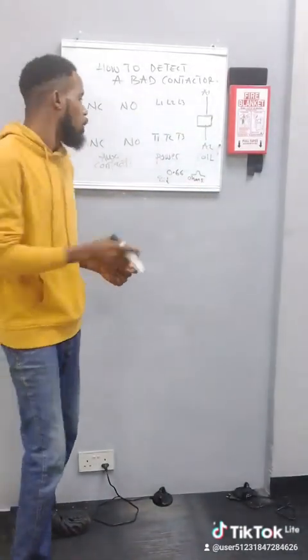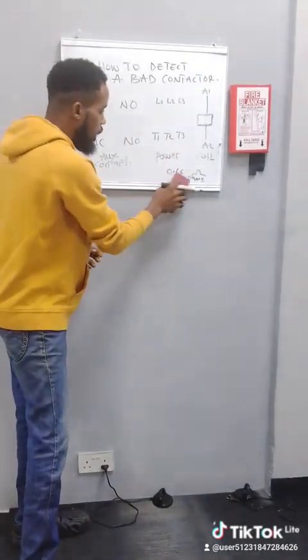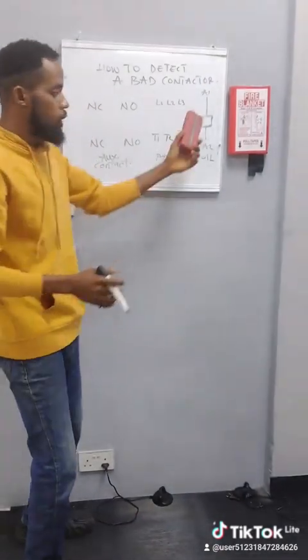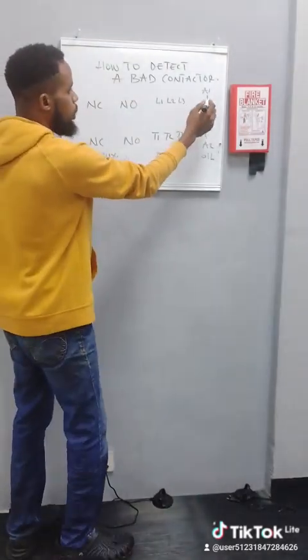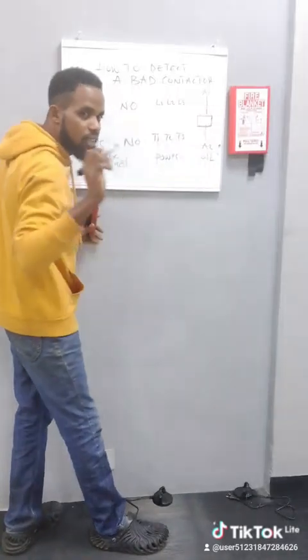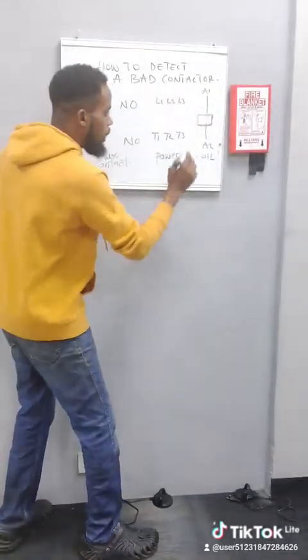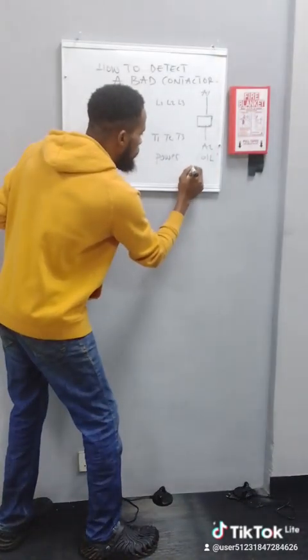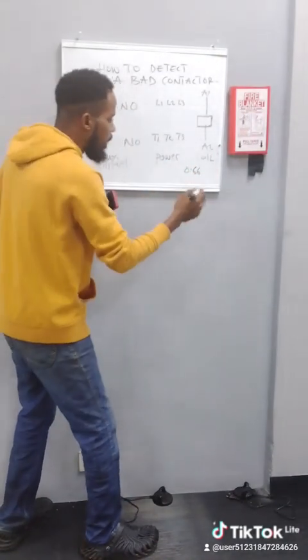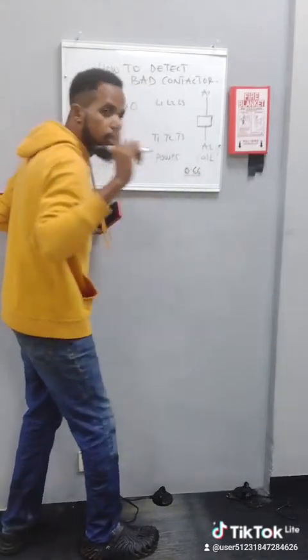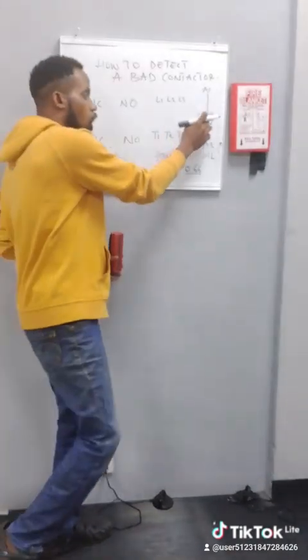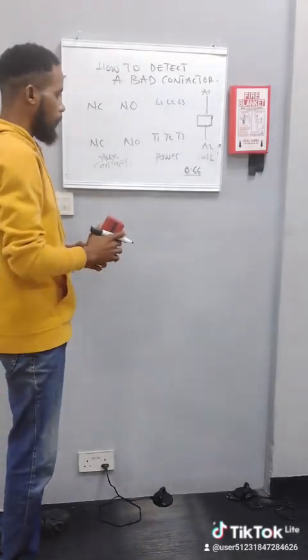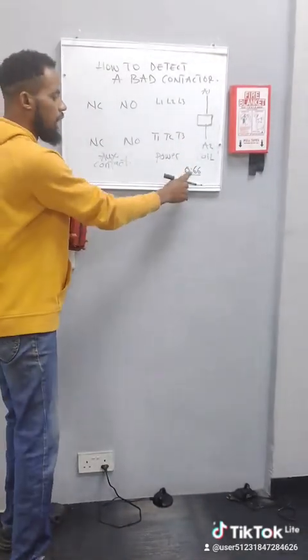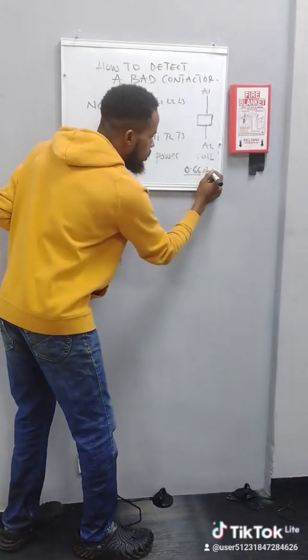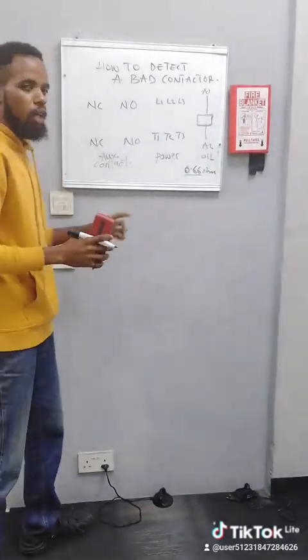So my brother, my sister, you need to change the contactor. After checking the resistance between the A1 point and the A2 point, the resistance, not continuity, your resistance value here will be 0.66. It might be 0.5, but if it's 0.6, you are safe. Your contactor is okay. But if it's less than 0.6, that means your contactor coil is bad. Take note, your contactor coil is bad if it's less than 0.6 ohms.